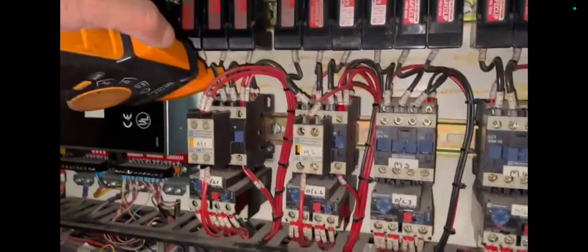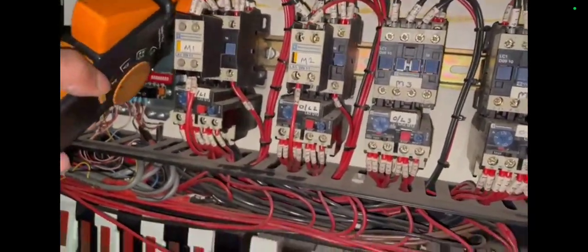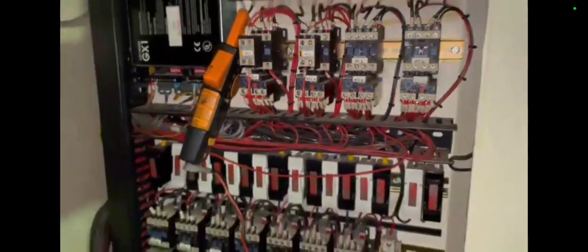The readings we require. So now I'm checking pump one, phase two. And we have 1.4, which is very high for a new pump that's gone in, and that phase is out of kilter with the first phase.